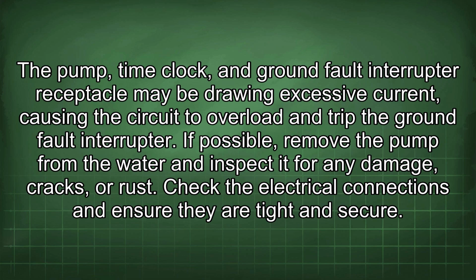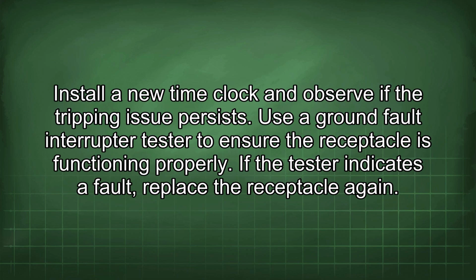If possible, remove the pump from the water and inspect it for any damage, cracks, or rust. Check the electrical connections, then ensure they are tight and secure. Install a new time clock and observe if the tripping issue persists. Use a ground fault interrupter tester to ensure the receptacle is functioning properly. If the tester indicates a fault, replace the receptacle again.